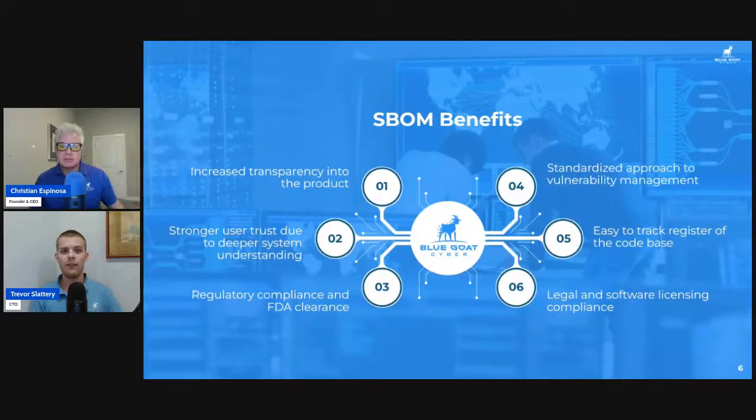Now, a little bit of an obvious benefit is the regulatory compliance and the FDA clearance. It's a requirement to have SBOMs within any medical device that is being submitted to the FDA at this point, unless you're effectively using no code within your product. Having this compliance checkbox and being able to provide assurance to the FDA that you are adhering to their guidelines, adhering to the FDA guidance on cybersecurity, is a great way to ensure a smooth process through your submission without any additional information requests.